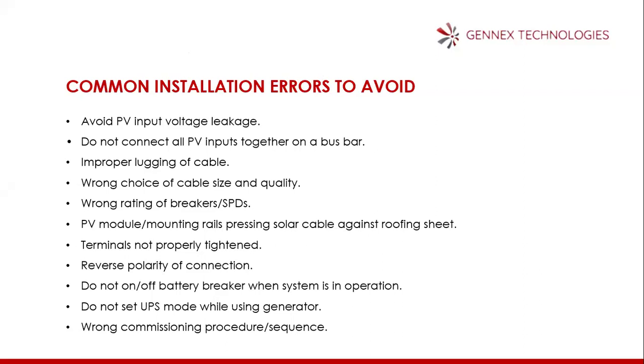Do not switch the battery breaker on or off when the system is in operation. When the inverter is working, somebody just comes in and switches off the battery breaker. This is absolutely wrong. Do not set UPS mode while using a generator. This inverter has a function, part of the settings that you have to engage if you must use a generator, labeled as generator in operation or something like that. You select that so that when you are using a generator, which has noise, the inverter will be able to accommodate all that noise and still work properly.